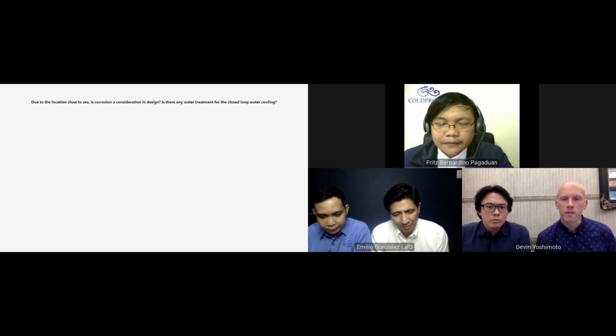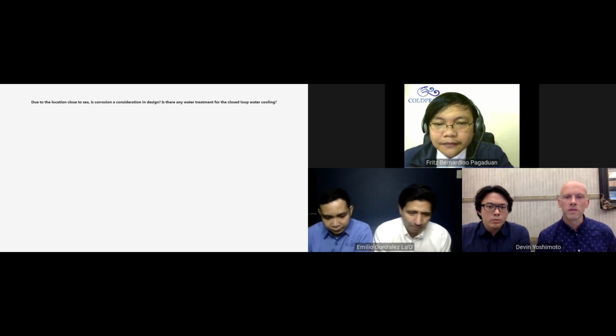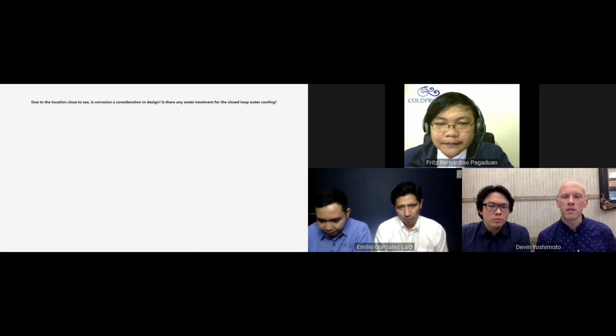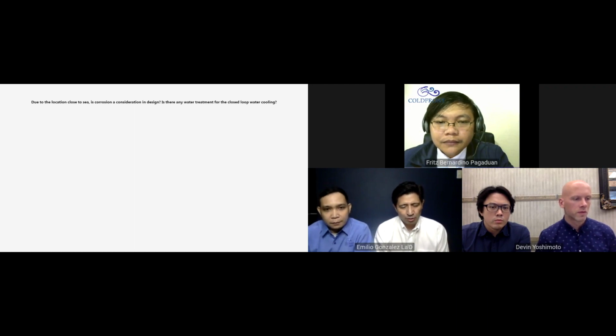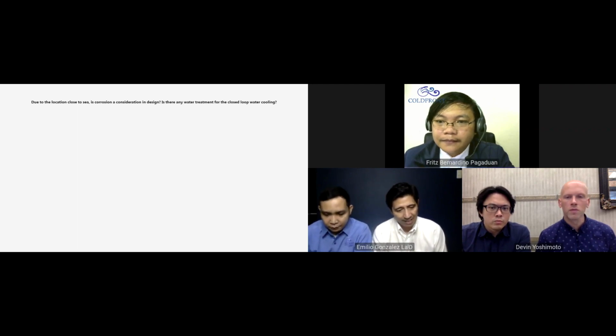Let me add real quick a little bit to that. As Fritz said, moisture is a big concern all over the Philippines because of the high humidity here. As Fritz mentioned, we use aluminum piping and demineralized water glycol to ensure no foreign object or scaling happens inside. And the dry coolers themselves are coated, called bluefin coated. Basically, there's a salt waterproofing put onto the dry coolers to prevent corrosion and allow them to last a bit longer.